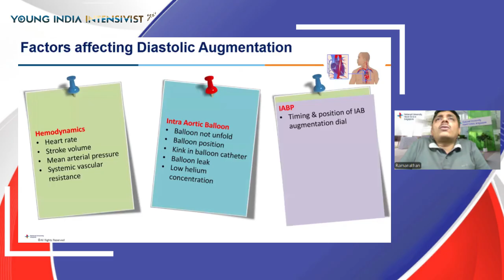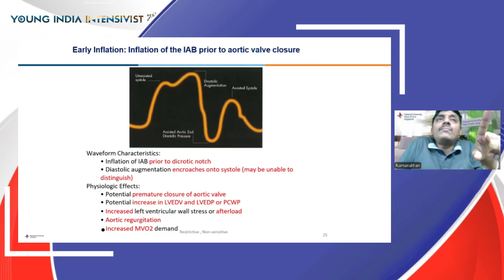Now, what are the important troubles that the IABP machine usually tends to alarm for? One of the things you may come across is an early inflation of the balloon. It happens before the dicrotic notch. The physiological effect is a premature closure of the aortic valve, causing increased LVEDP or PCWP. This is not good for the heart because the very idea of putting in a balloon pump was to reduce it. It increases your oxygen demand, so this is something you need to detect early and make corrective measures.